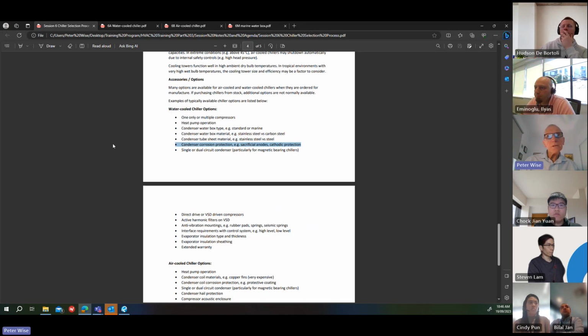Now, condenser corrosion protection. If you have stainless steel components, you haven't got much to worry about. But if you've got steel, an option could be sacrificial anodes. These can be supplied with the chiller. Or you can get cathodic protection, which is an electronic system which will be supplied probably not by the chiller company, but by another company. Might be the controls company, might offer you that. So keep that in mind.